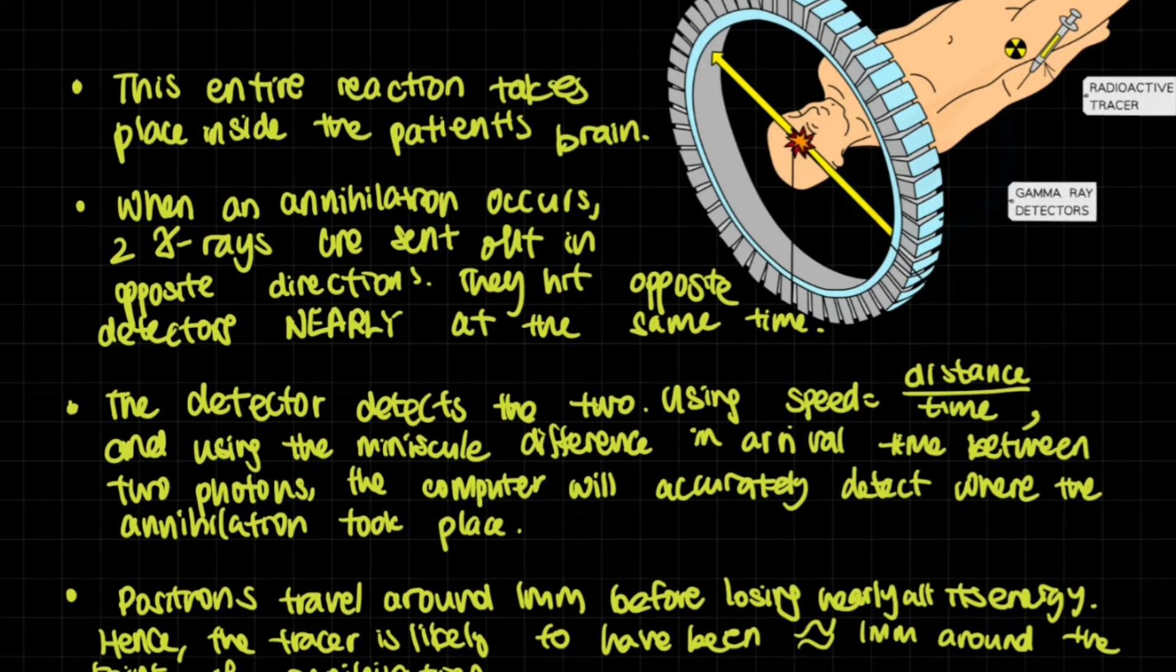Well, this entire reaction takes place inside the patient's brain, or wherever else there is a cancer cell. But let's say that this is like a brain scan. The patient is actually inside this ring of gamma ray detectors, and they're all segmented. They're all separate gamma ray detectors. When an annihilation occurs, two gamma rays are sent out in opposite direction. They hit opposite detectors nearly at the same time, but not exactly.